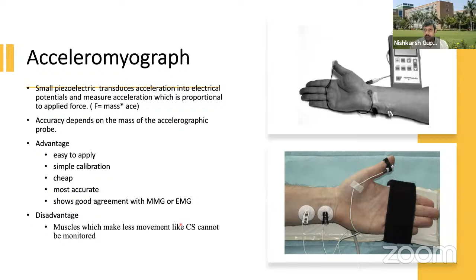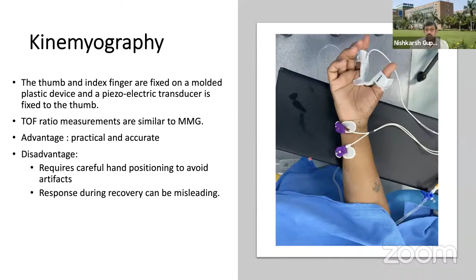Then we have kinemyography. This usually comes with a Dräger machine or newer anesthesia machines which have an inbuilt neuromuscular monitor. We can see the thumb and index finger are molded in a preformed device which is usually of plastic or rubber, and there is a piezoelectric transducer fixed to the thumb. The ratios are similar to MMG, and it is a practical and accurate alternative for monitoring NMT. The disadvantage is that it requires careful hand positioning to avoid artifacts, and the response sometimes can be misleading.